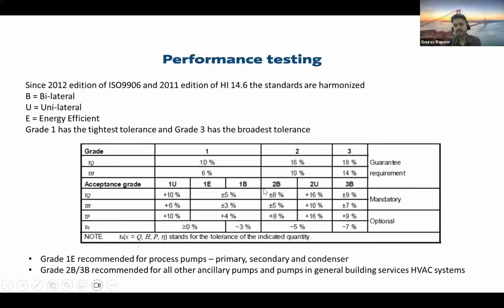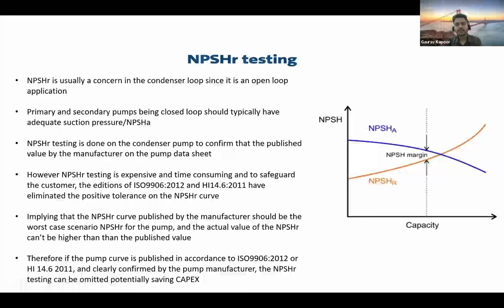Now, the other important point is NPSHR. You all may think HVAC is a closed network and you do not need NPSHR testing. No, on the cooling tower side, the condenser pumps are open loop. So it is very, very important to also have NPSHR testing required. If the height difference between the cooling towers and the condenser pumps is not much, it is recommended to also have an NPSHR test done.